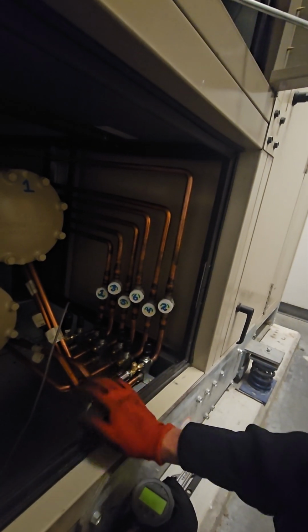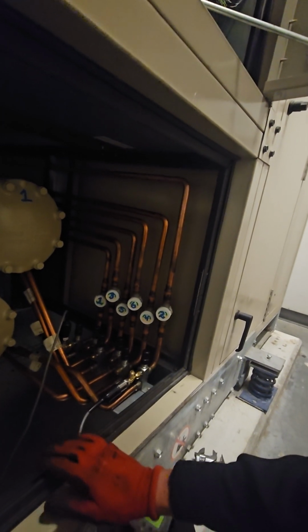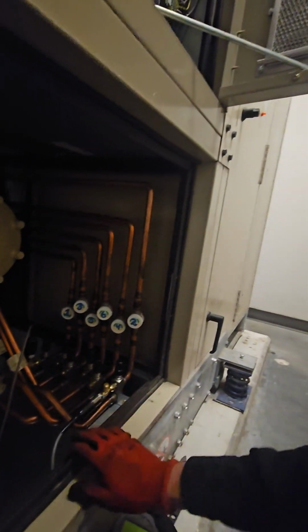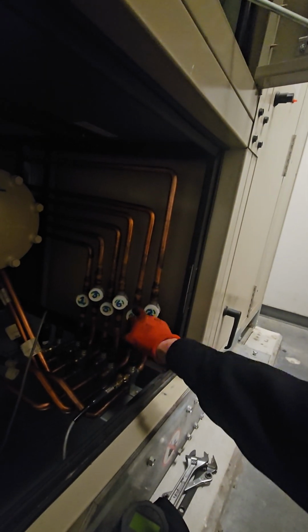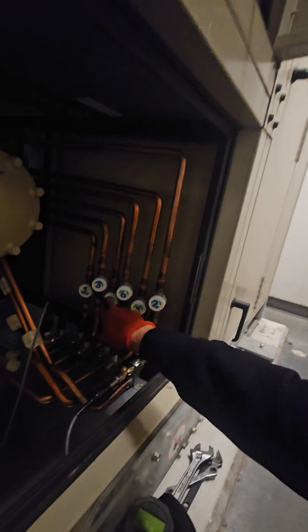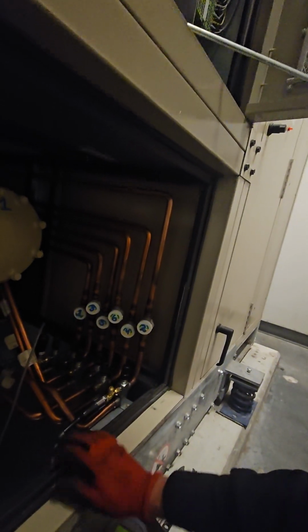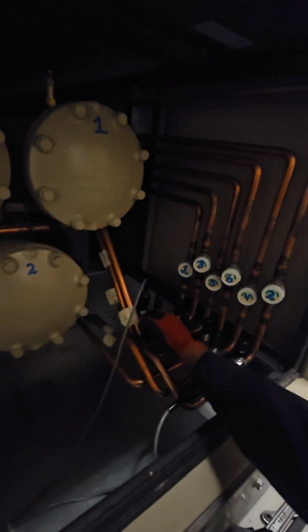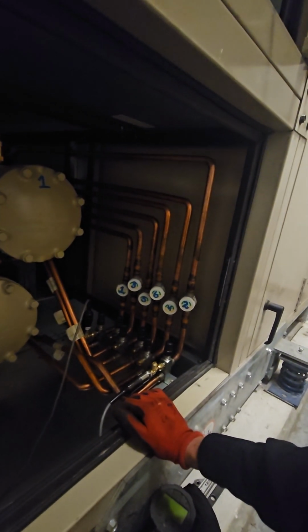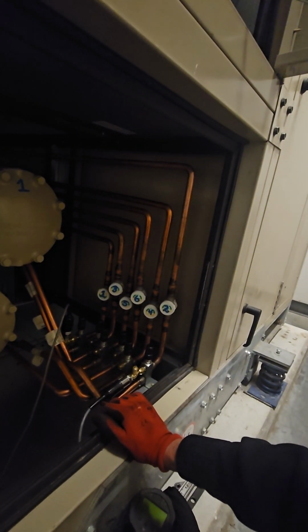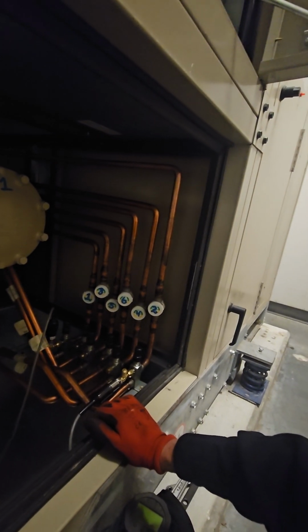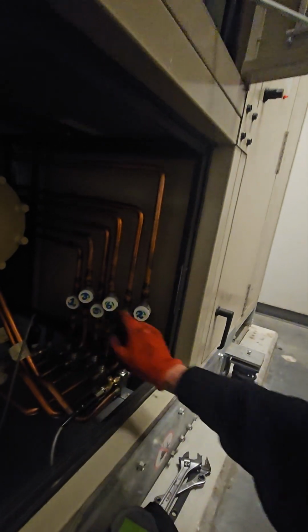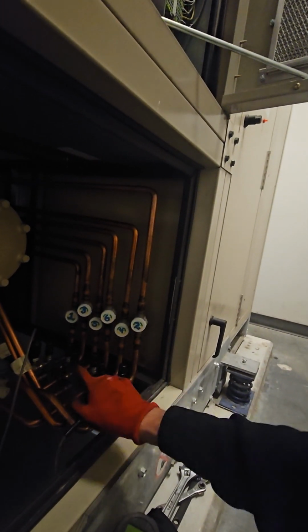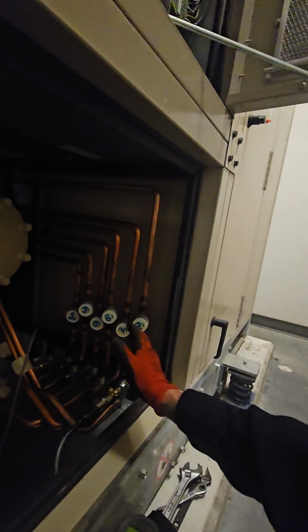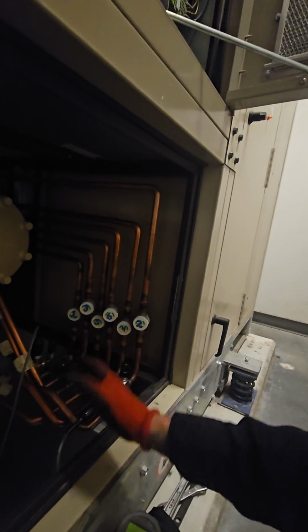No matter what, each and every time one of these starts up, it's either going to start number 1 or it's going to start number 2. It cannot start 3, 4, 5, or 6 first, because neither one of those is controlling the water regulating valve, and they will trip on high head because the valve will be shut. Just thought I'd share that. So yeah, 1 or 2 turn on first, and then it starts throttling 3, 5, 4, and 6. Hopefully that made sense.